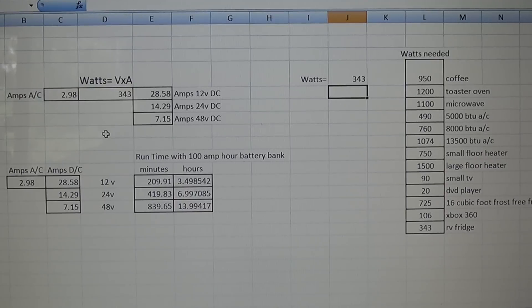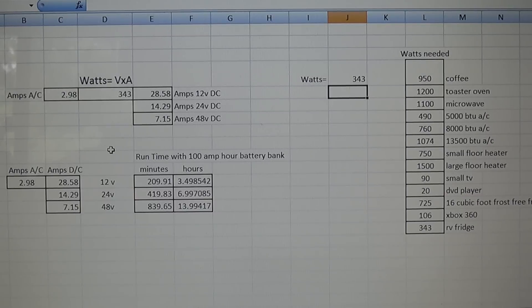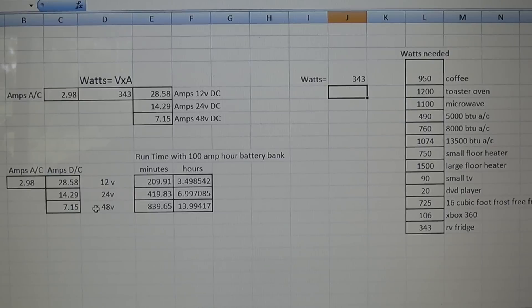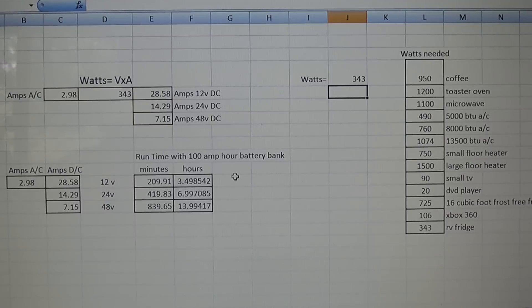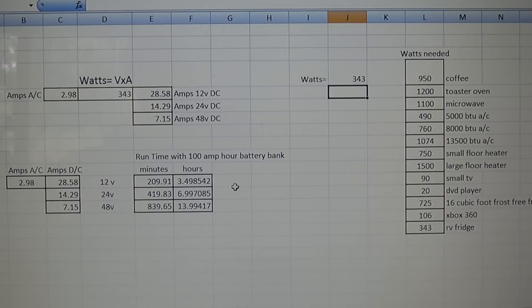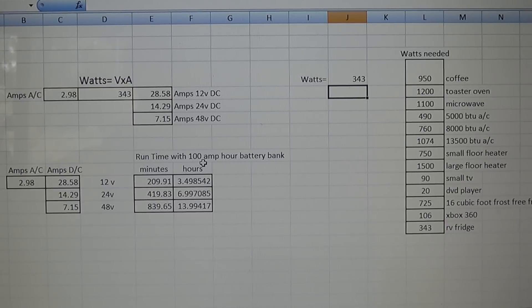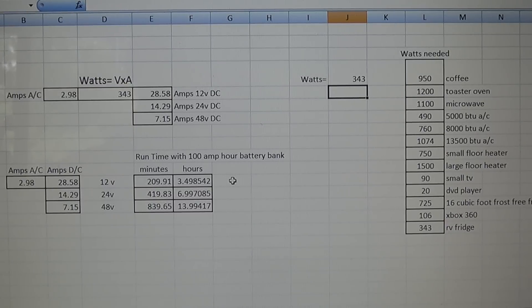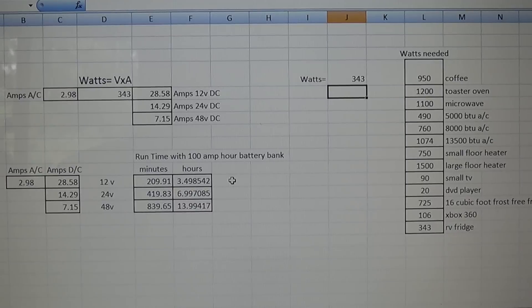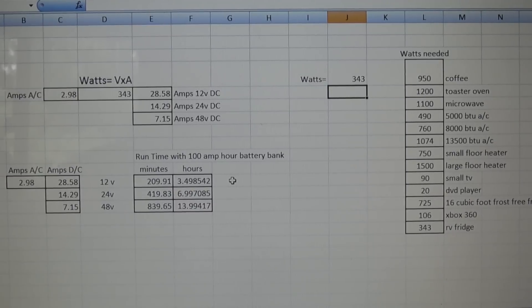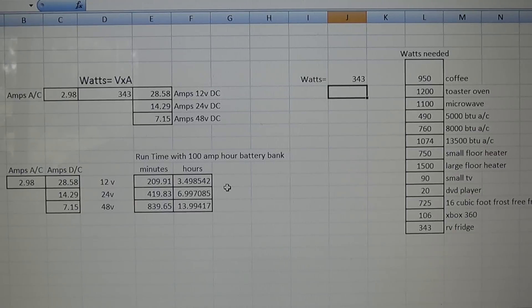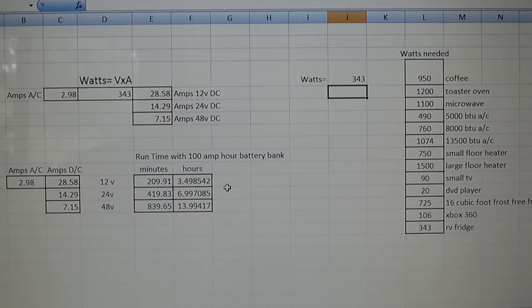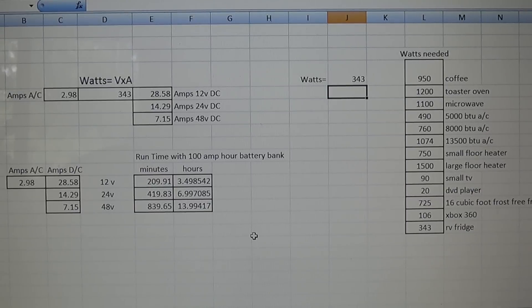The thickness of the wire - you can use much thinner wire, and there's all kinds of advantages to it. What I've done is I have a 400 amp hour bank, and then at 50% that's 200 amp hours, but I really don't want to get below 75%, so that's 100. I thought 100 worked out really well because if you have a 12 volt system, it would take a lot of batteries to get to 100 amp hours. If you have a 50 amp hour thing, you just cut these numbers in half or write your own spreadsheet.